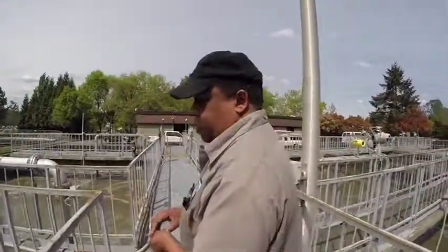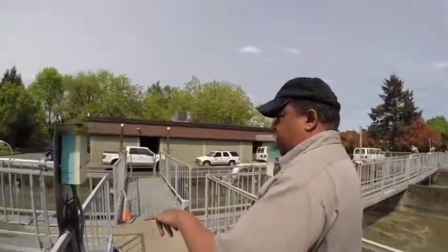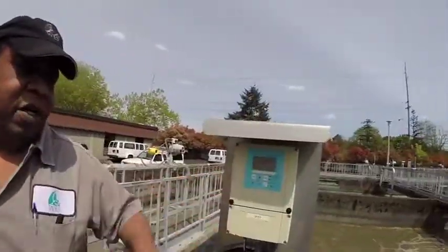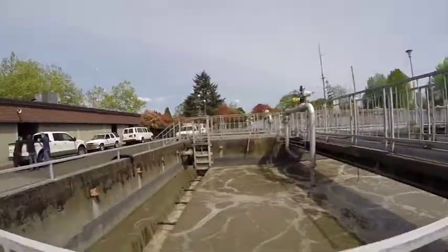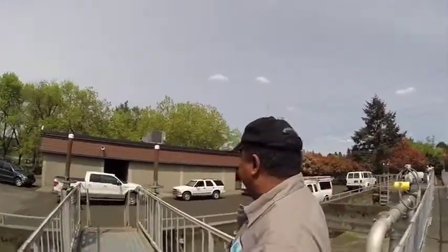So what type of aerators do you have under there? These are coarse bubble diffusers. And now look at that. Our aeration's dropped down to 0.55 and 8.9, so we really dropped off on our air. Because I don't like to carry air over to the secondary clarifiers. All your work should be done here, not over there. So that's why I do not try to carry air over that far.